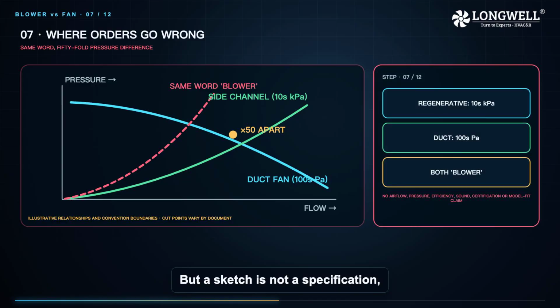But a sketch is not a specification, and this is where orders go wrong. A regenerative blower, a side-channel machine built for tens of kilopascals, is a completely different machine from a centrifugal duct blower at a few hundred pascals, yet both answer to blower. Order by word instead of by duty and you can be wrong by a factor of 50 in pressure. The word narrows the family, only numbers select the machine.